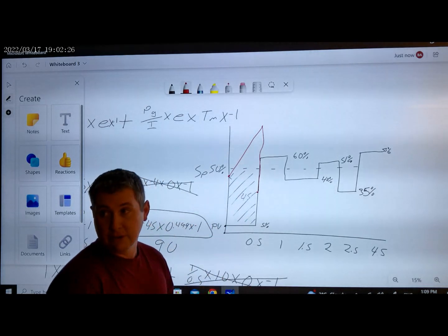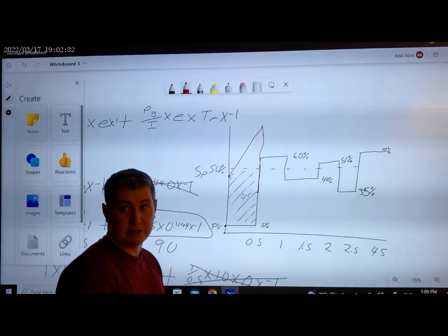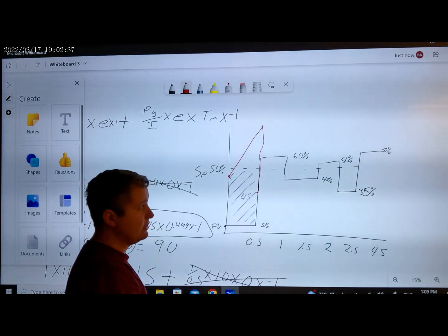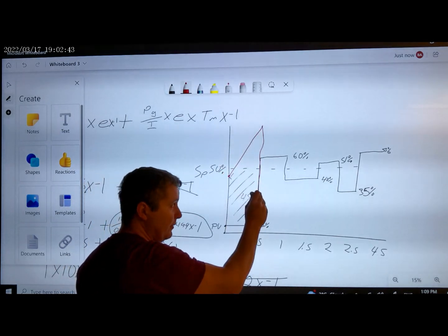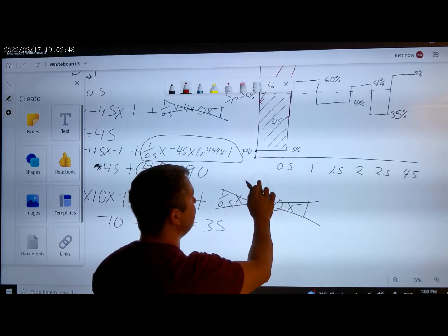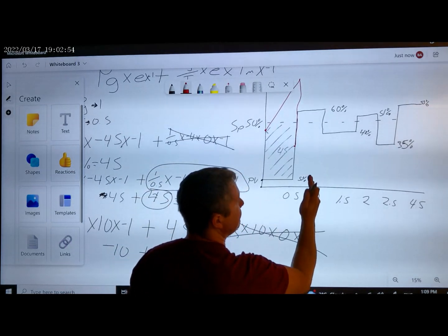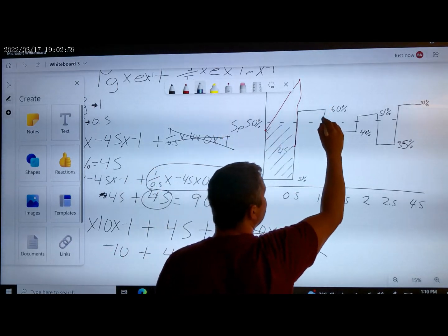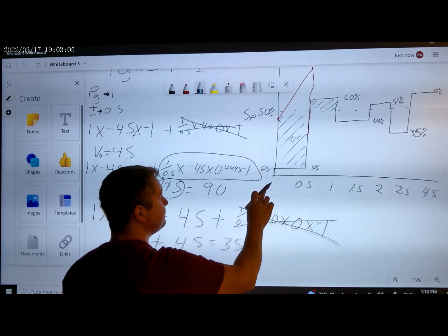In reality, we don't have it hooked up, so our process variable did not increase. But it kept trying to increase the input to our system, trying to get that PV to come back to its set point. But then once we jumped up to 60, our output dropped down drastically. Because it said, whoa, you're really getting close there now. So now we want to calculate it at just before it hits the 1 minute mark, before it drops down. Because we want to calculate what our integral is going to do to us now. Okay? That's what we're calculating.